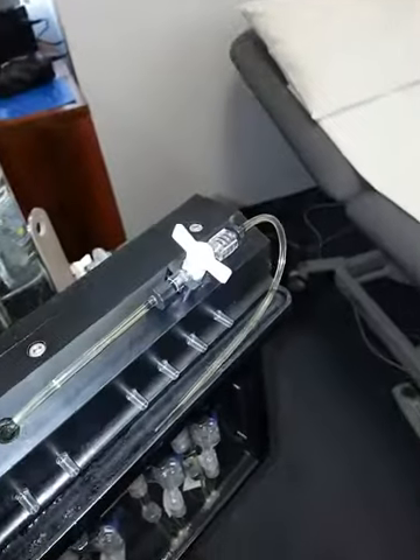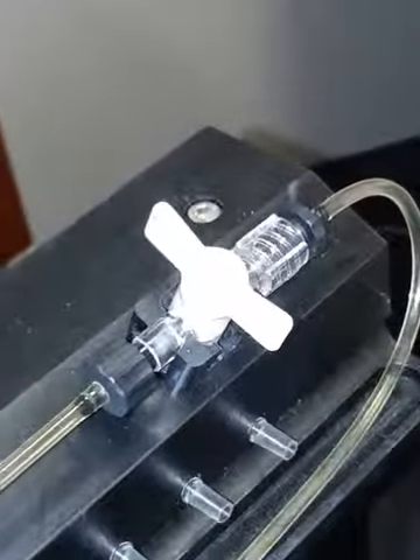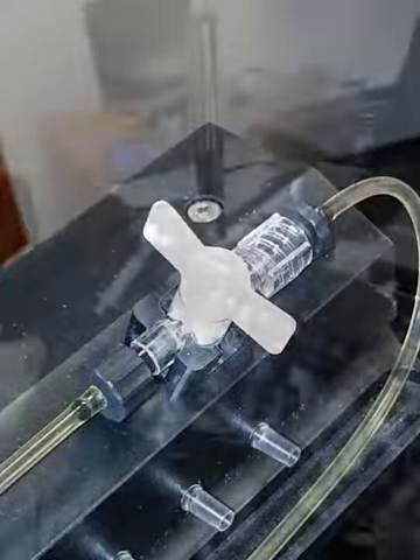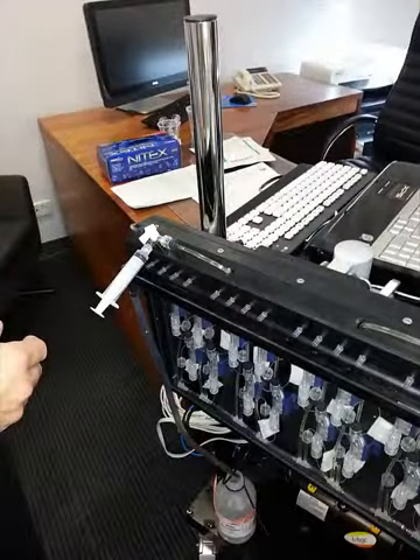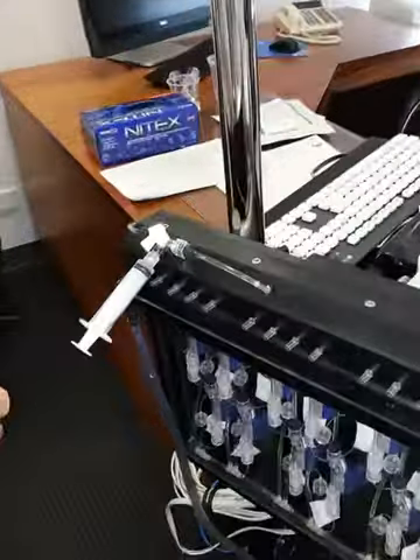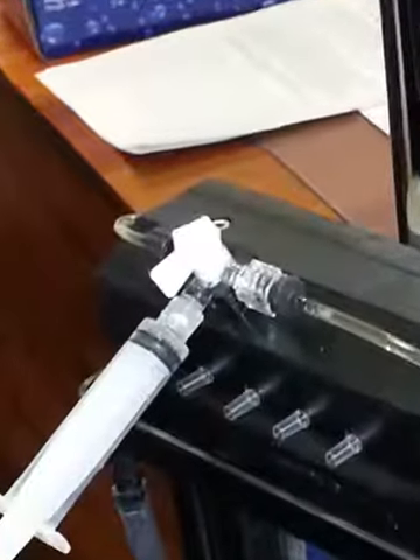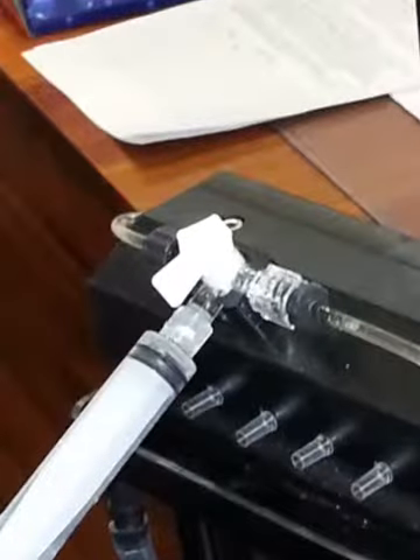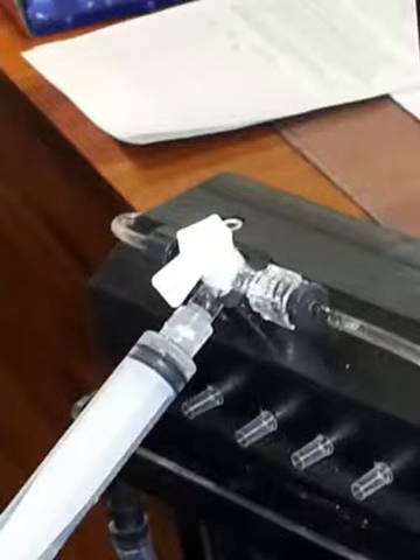Repeat the process of filling the syringe with water and gently irrigating the manifold until no further air bubbles are passing through. Once you have cleared the manifold and tubing of air, close the tap at the outlet of the manifold. Leave the syringe attached and turn the tap so that the lever faces the syringe. This will allow water to perfuse into the manifold from the water reservoir.